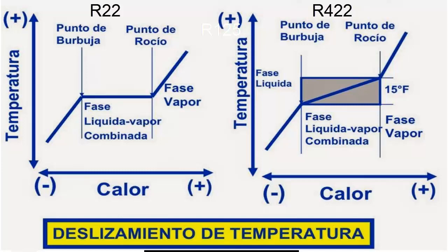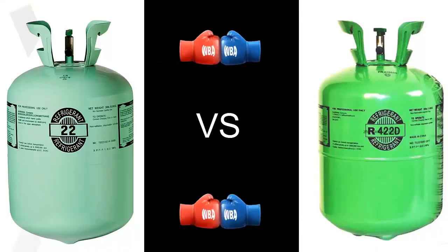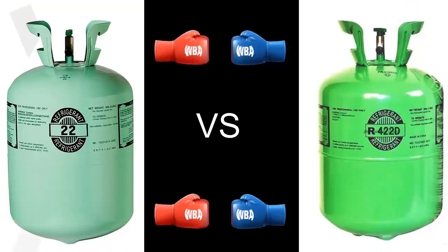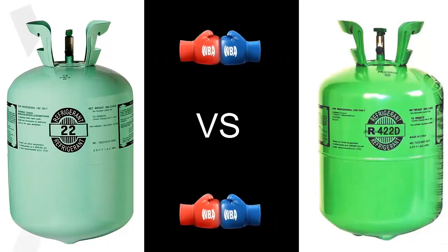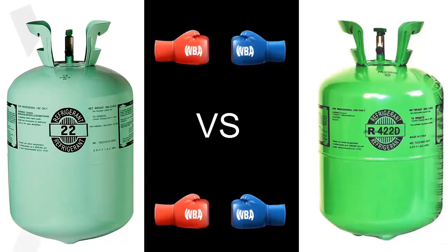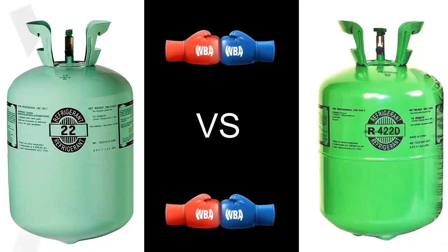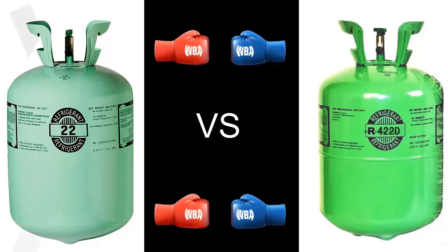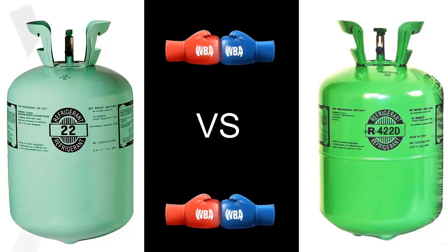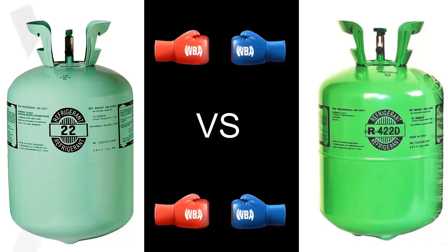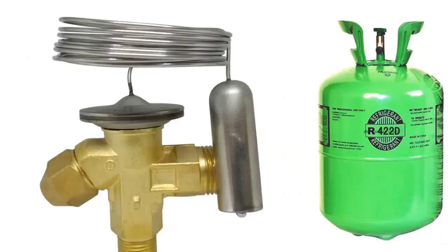In terms of cooling capacity, the R422 family tends to be slightly lower than that of R22, usually with less than a 5% difference. In some cases, using gases from the R422 family may require adjusting or regulating the expansion valve.